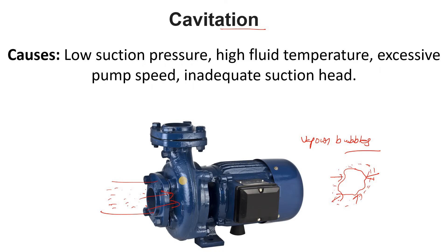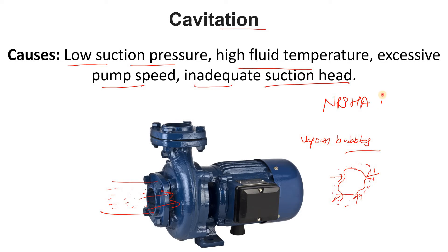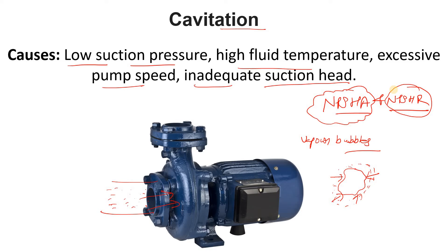The causes of cavitation include low suction pressure, high fluid temperature, excessive pump speed, and inadequate suction head. NPSH — net positive suction head available and required — plays a very important role. When sizing a pump, NPSH available is calculated by the process engineer and NPSH required is given by the pump manufacturer.